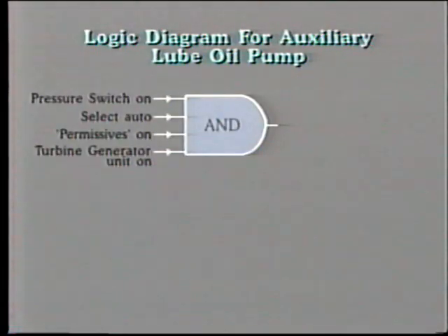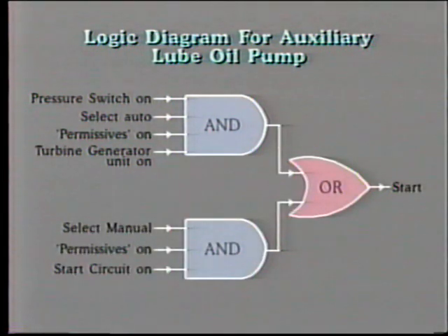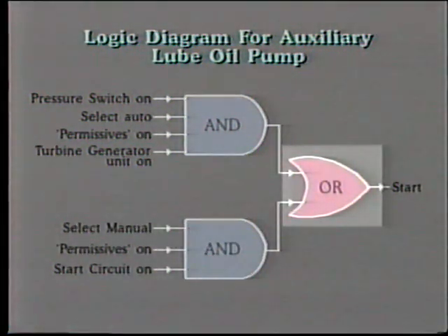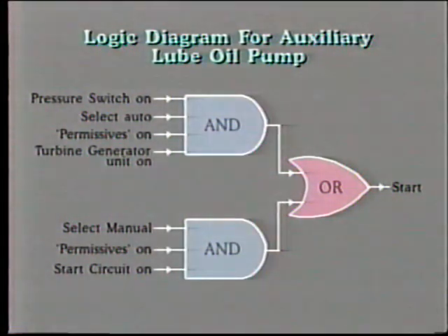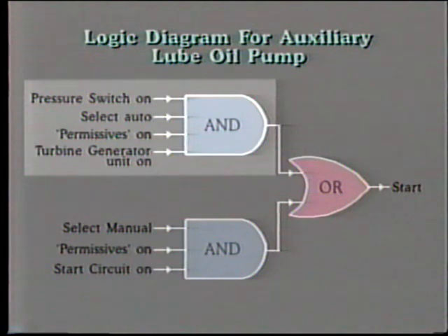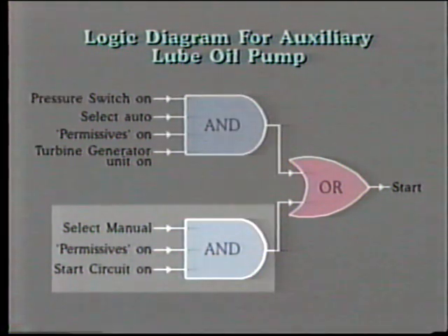So now we have to introduce another element to the logic diagram. This is the OR gate. The auxiliary oil pump can be energized by a signal from either the auto start element or the manual start element. And what conditions must be satisfied for the manual start? Well, in this case, we need the auto manual switch to be set to manual, and the permissive contact to be enabled, and the starting circuit from the manual switch to be energized.